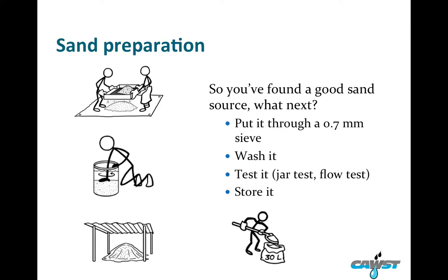The water you dump out of the bucket should still be a little dirty when you finish washing the sand. You do not want to wash the sand until it's completely clean. You do need to maintain some of the fines or the silt. Finally, you store the sand in a clean, dry, protected place. After all that work, you don't want wind blowing leaves and dust into your sand or dogs contaminating it. And I've also run into problems with children liking to play in it. Now you can also bag the sand for transportation. You'll need about 30 liters of sand per filter for the concrete filters.